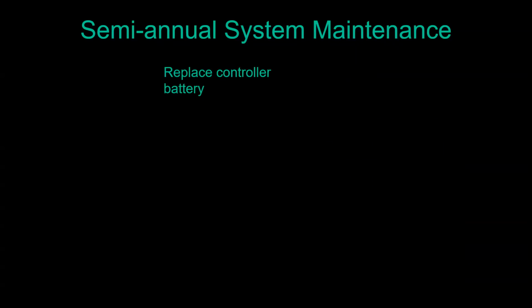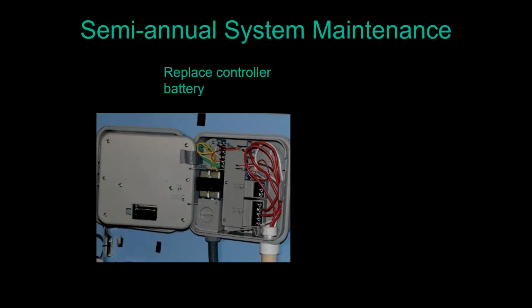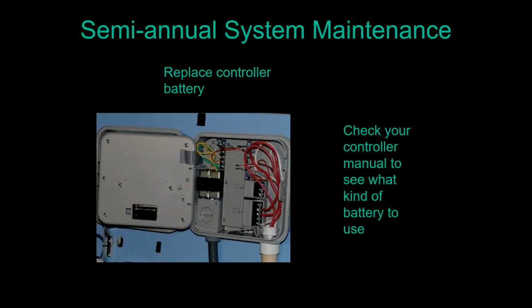About twice a year, if your controller uses a 9-volt backup battery, you want to replace that every 6 months. Do check with your controller manual. Some of your high-end controllers actually provide a trickle charge, so you use a rechargeable battery in those, and every 6 months is too often to change it if that's the case.